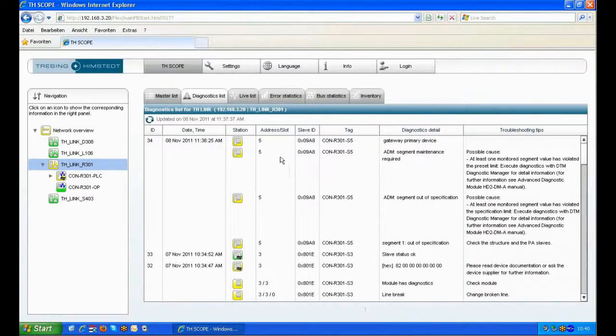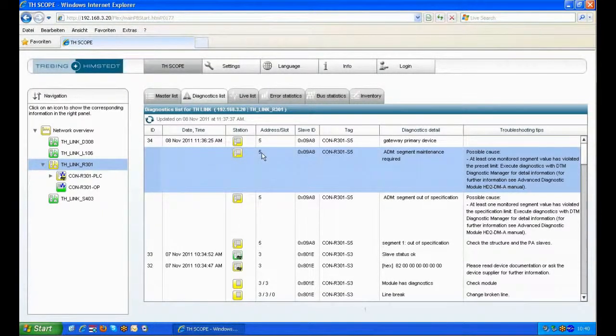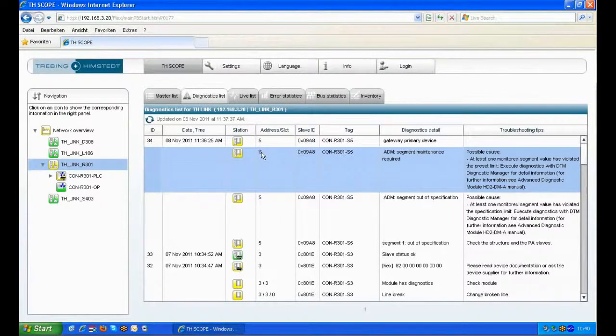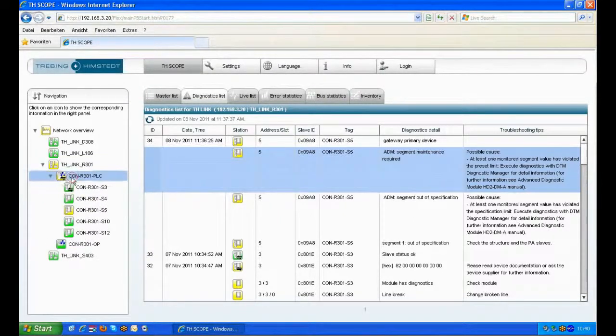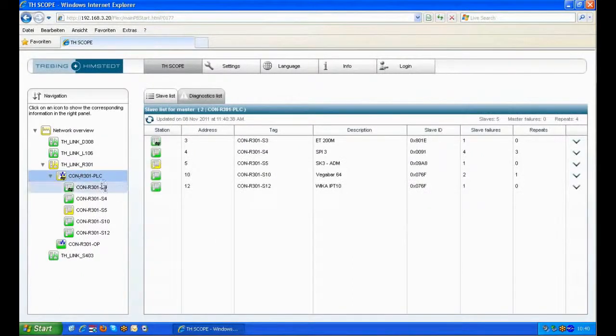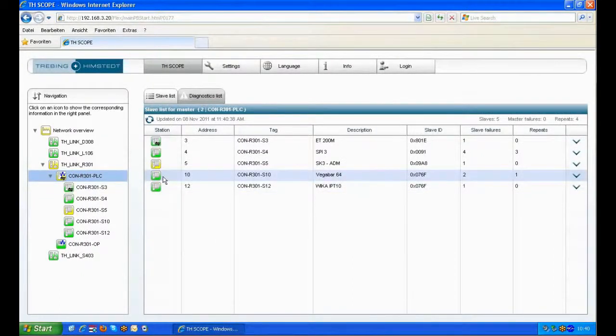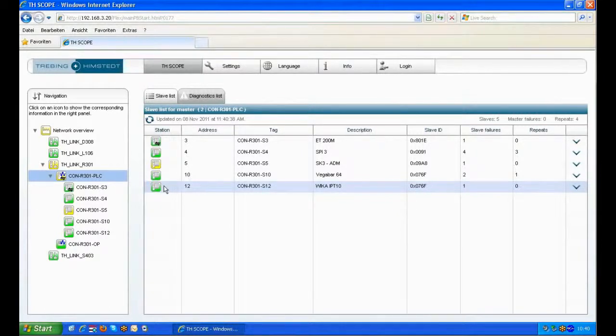In this case we see diagnostic information from our SK3 on DP address 5. Going deeper into the network structure we see the PA devices on PA address 10 and 12 behind the SK3 because it's a transparent coupler.